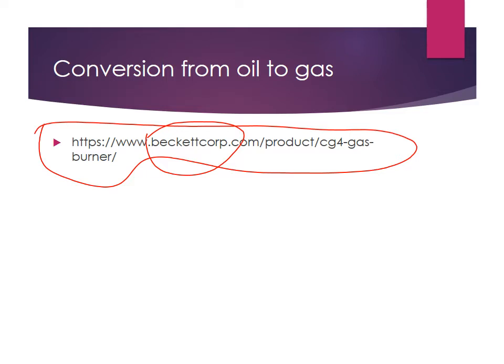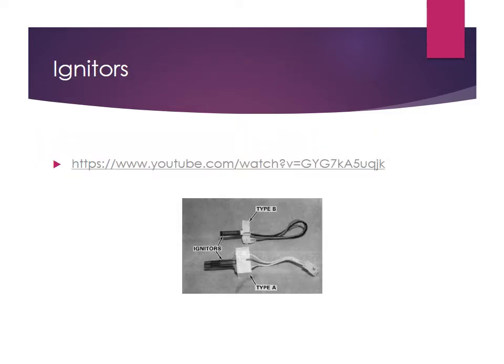Igniters for oil are different than for gas. Before, we had to atomize oil into small droplets; now we have gas, which is very easy to ignite — it doesn't take much, just a very small spark. There are two types of igniters: some produce a spark and some are a heated glow stick, called a glow igniter. This is a heater that gets very hot, glows, and will ignite the gas. Gas ignites at a lower temperature than oil, and since it's in gaseous form it's easy to ignite.